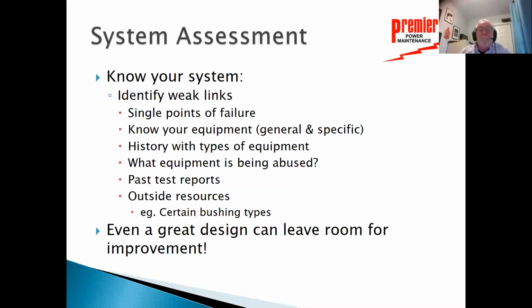We need to know our equipment. Generally, we pretty much always know what we have as a system, but for specific pieces of equipment, we need to understand the history with the types of equipment we've got. Most of us get in the mode where if we buy one transformer and we have good luck with it, we stay with that manufacturer, so we limit the number, and that's great, and that works very well. But we need to understand our equipment and the specific nature of those, and what kind of history we have with that particular piece of equipment, and keep that maintenance record on hand. What equipment do we have that we are really abusing at this point in time? And we all have systems where we do abuse part of our system, so we need to take care of that.